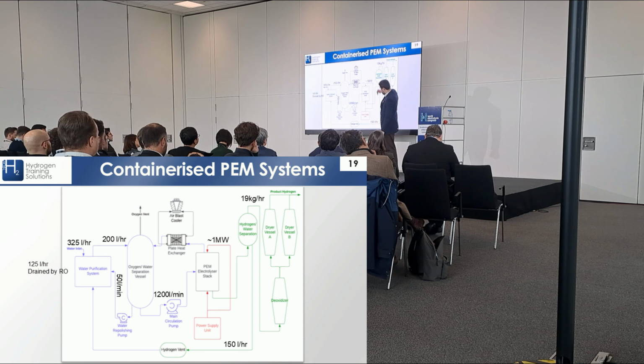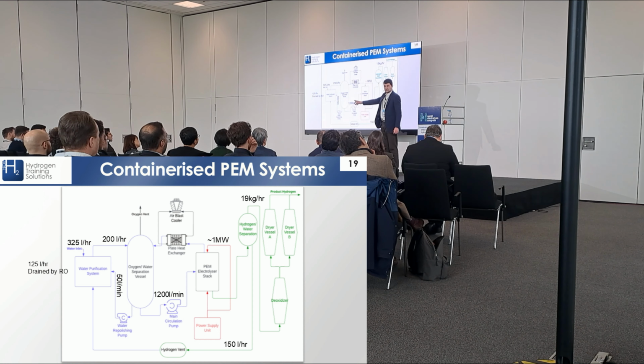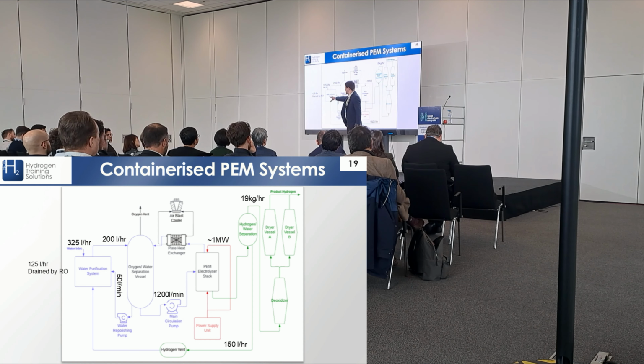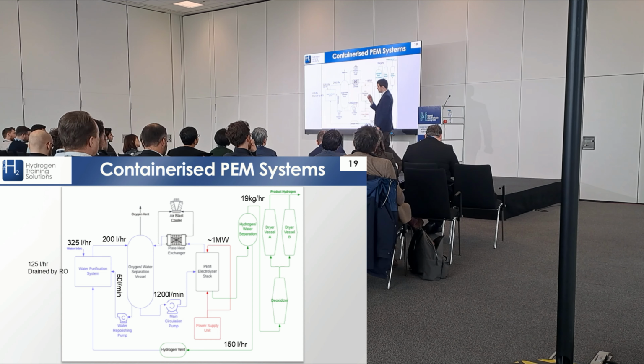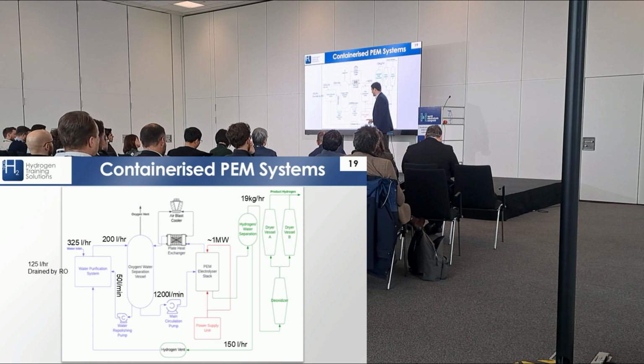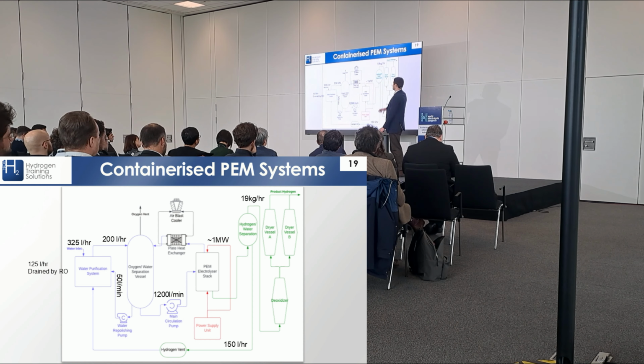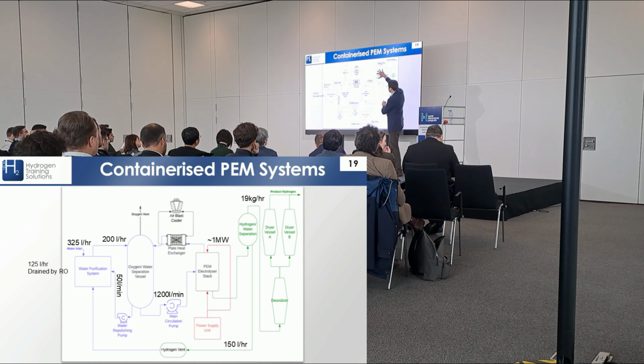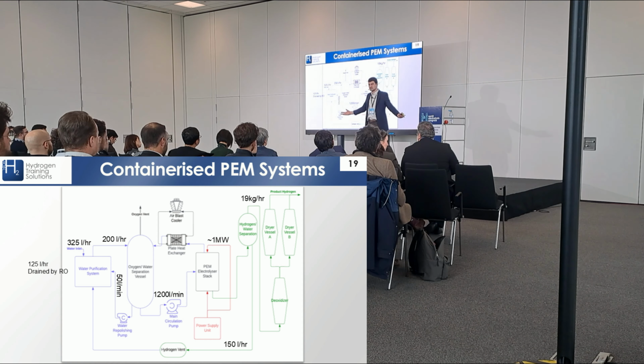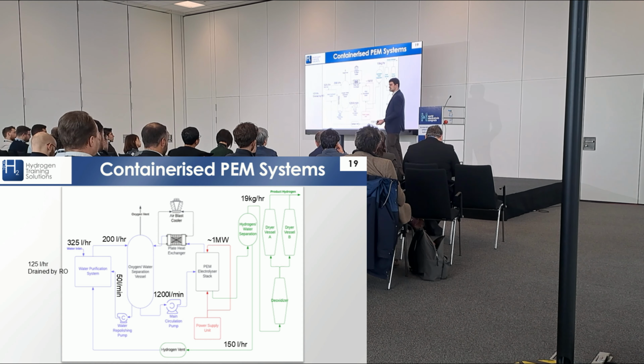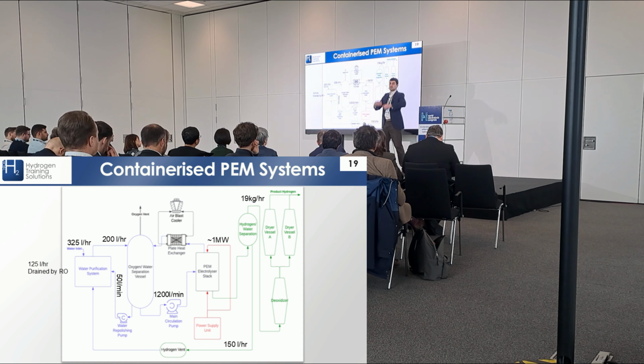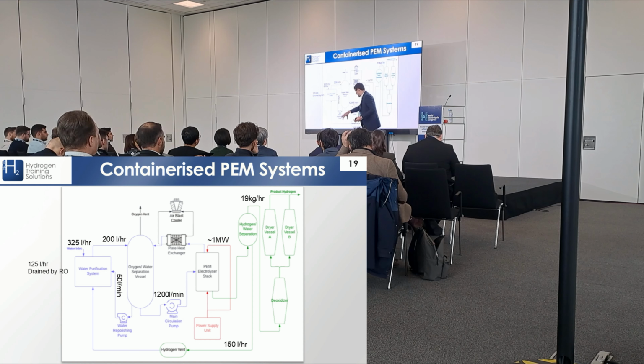We must have some way to vent out the hydrogen going back into the water purification system, because that system will have air and oxygen in it. We must make sure we're not putting any hydrogen back into it. So we need a vent system, because this hydrogen-water separation vessel is at about 30 bar, the typical system pressure on the hydrogen side. When you depressurize this water, hydrogen bubbles will come out all over the place, and you want that to happen in the hydrogen vent, not in the water purification system.